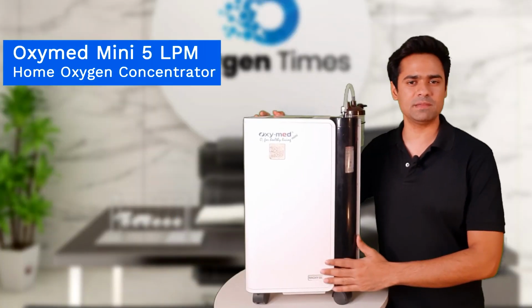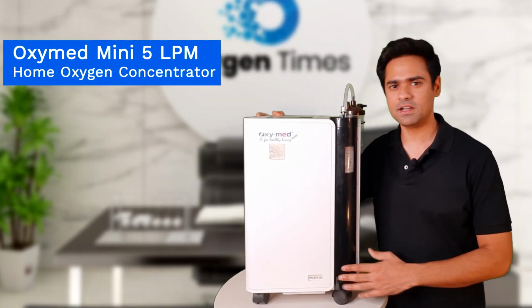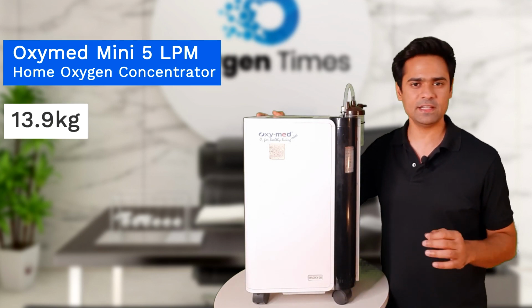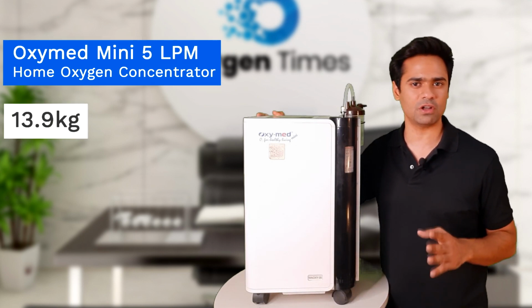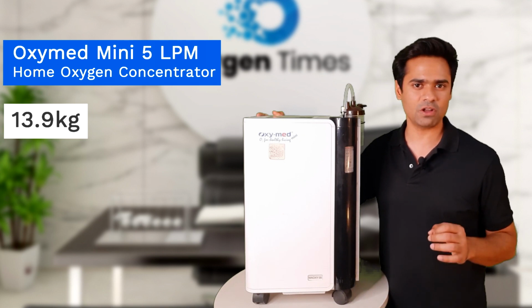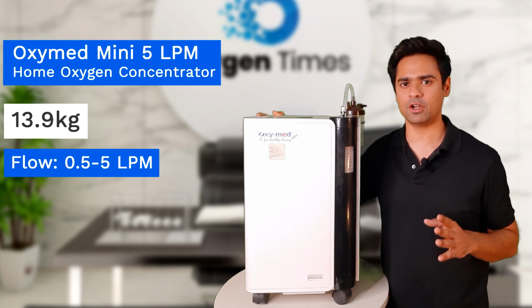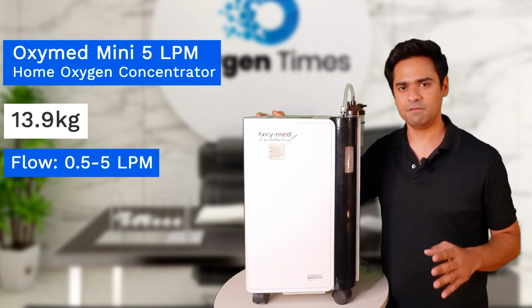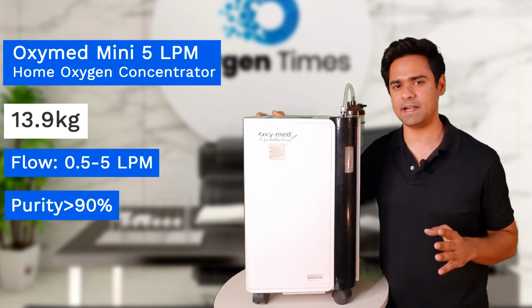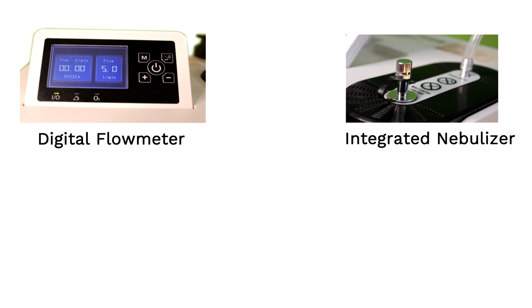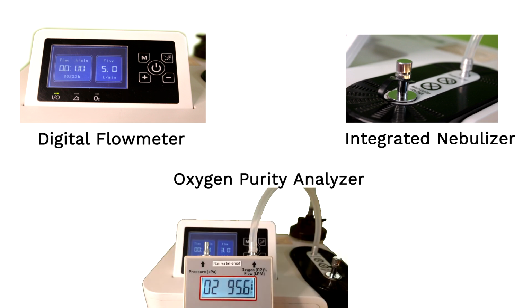This is the latest Oxymed Mini 5 LPM home oxygen concentrator. Weighing just 13.9 kgs, it is one of the lightest and smallest oxygen concentrators available in India. This concentrator delivers oxygen at a flow rate of 0.5 to 5 LPM with an oxygen purity of more than 90% at all flow rates. With promising specifications such as the digital flowmeter, integrated nebulizer, and oxygen purity analyzer, it has landed in the core of the Indian market, leaving even most of the well-established American oxygen concentrators behind.